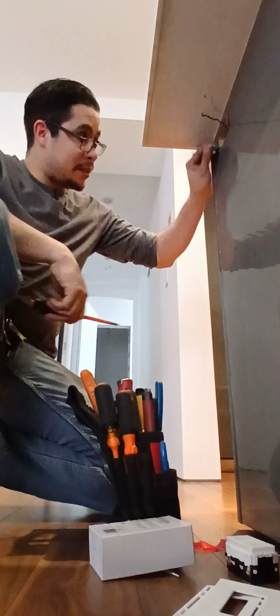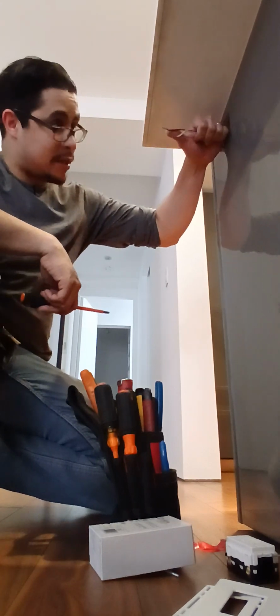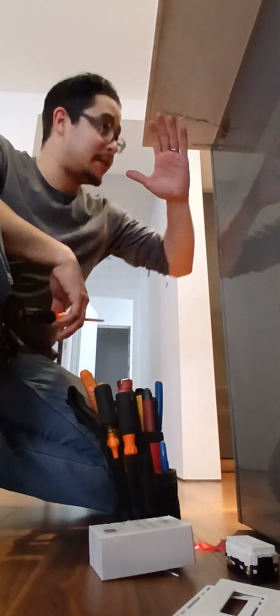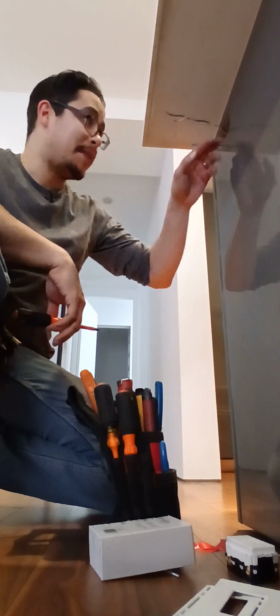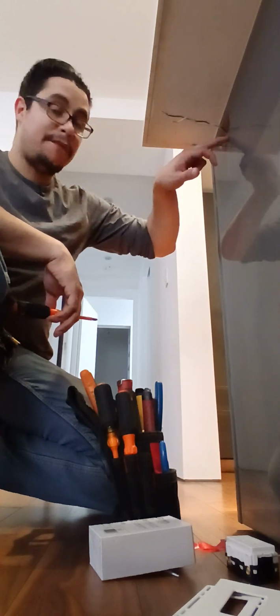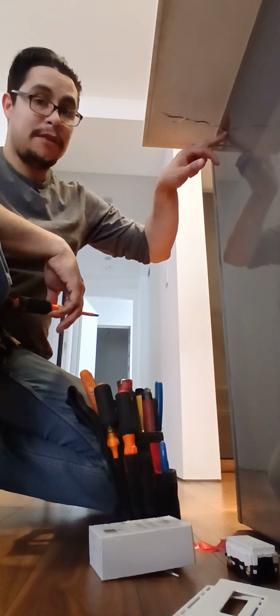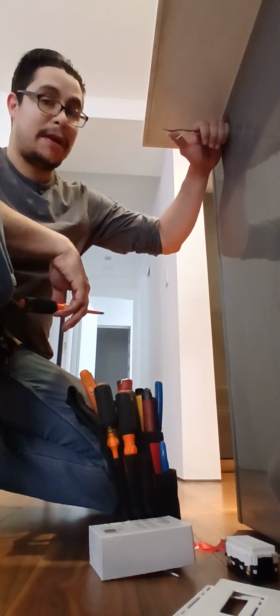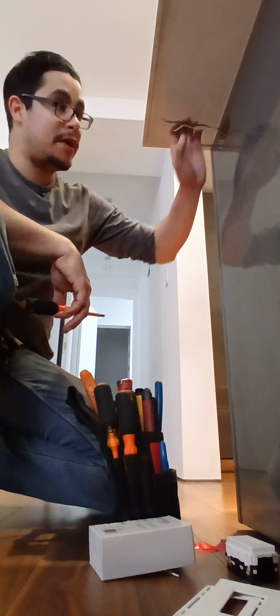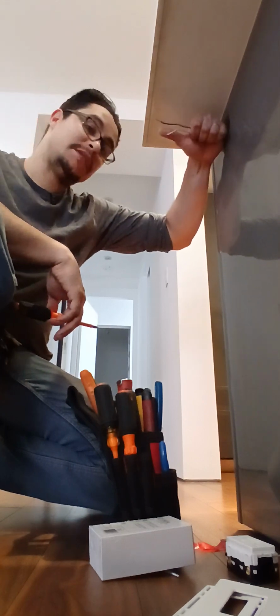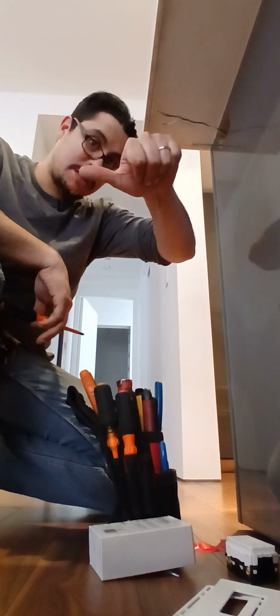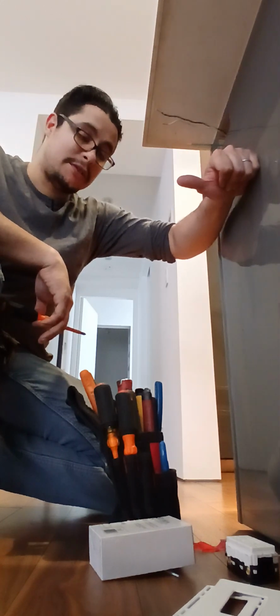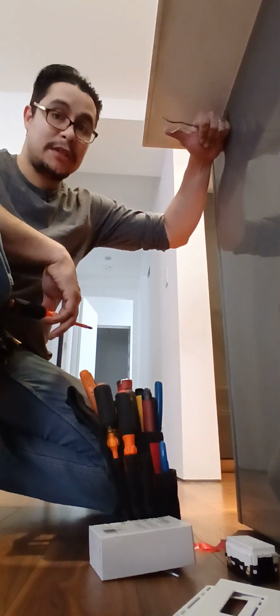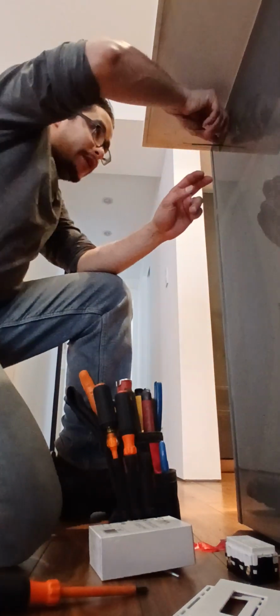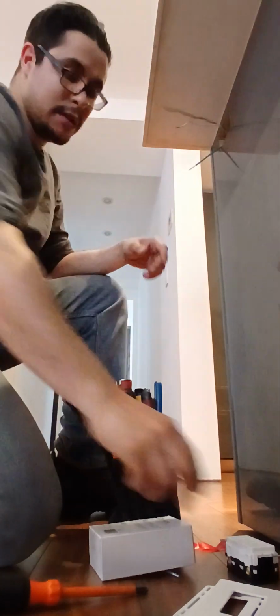Right in the same screw hole. Now as you can see, it comes up short. It's got to be 6 inches. So if you want to know how to measure 6 inches without a tape measure, the wires have to come at least 6 inches out from the surface of the box inside the wall or partition. Rule of thumb, do this and you've got your 6 inches right there, roughly 6 inches or more. That's okay, you're good. You want to have that little extra in there.